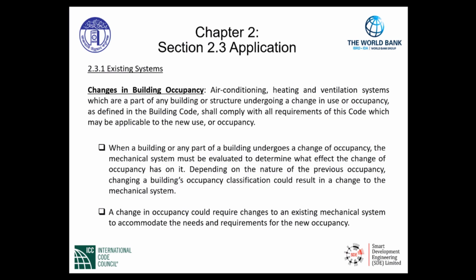Changes in building occupancy. Air conditioning, heating, and ventilation systems, which are part of any building or structure undergoing a change in use or occupancy, as defined in the building code, shall comply with all requirements of this code which may be applicable to the new use or occupancy. When a building or any part of a building undergoes a change of occupancy, not only the building but the mechanical system must be evaluated to determine what effect the change of occupancy has on it. And depending on the nature of the previous occupancy, changing a building's occupancy classification could result in a change to the mechanical system.